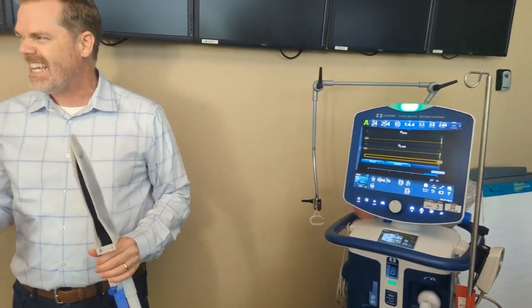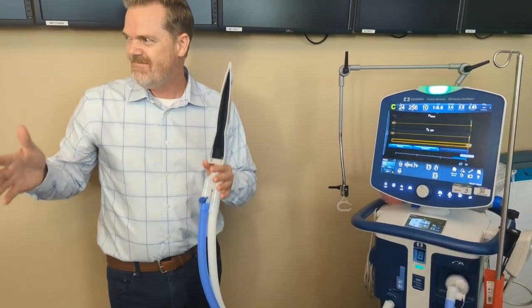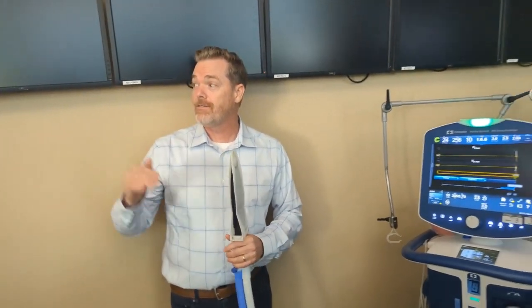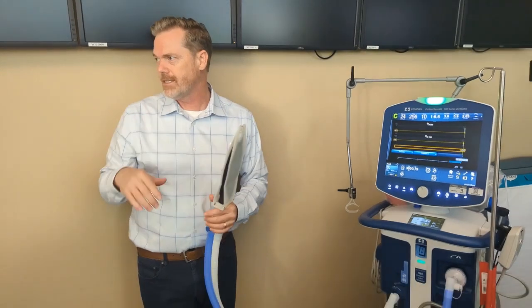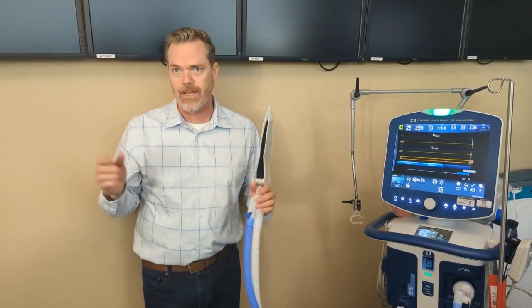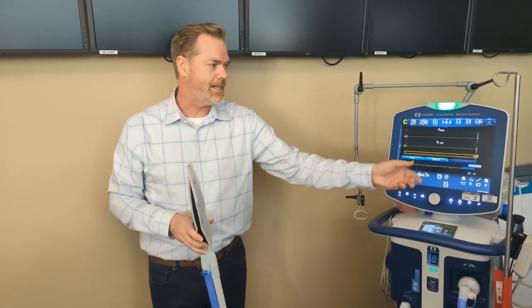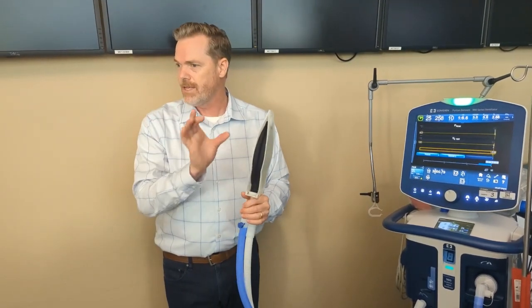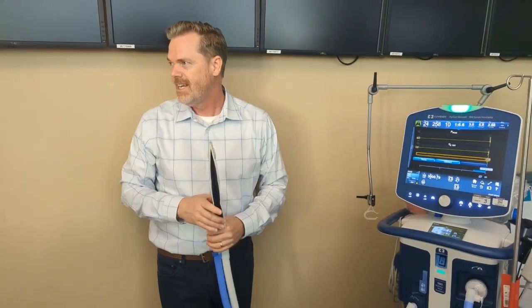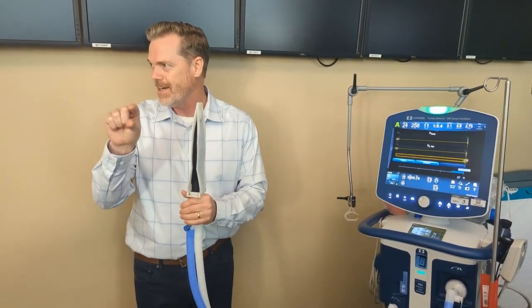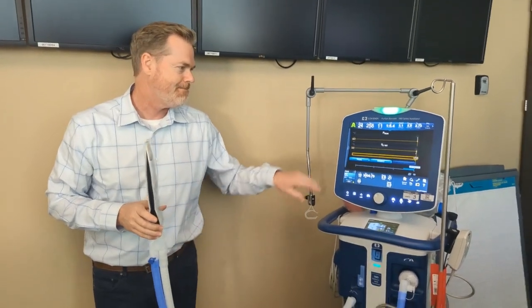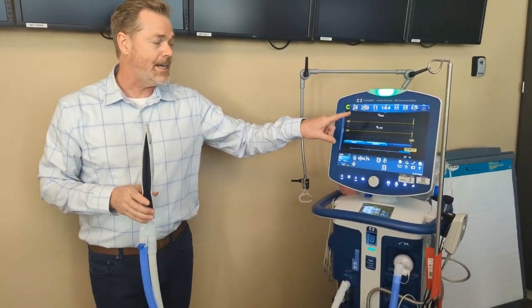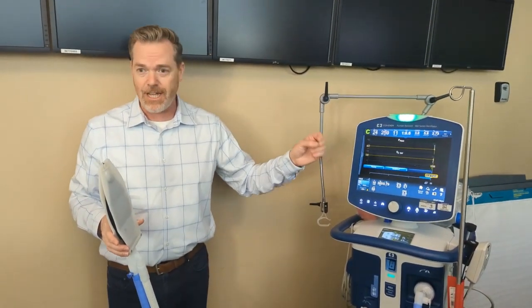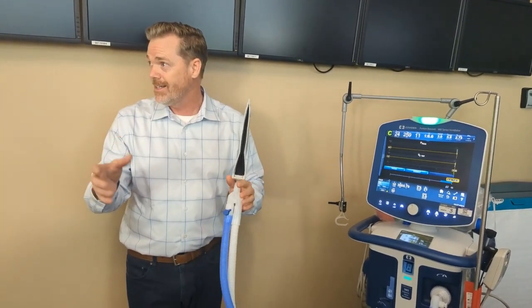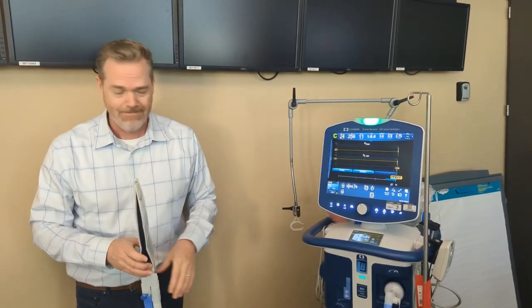If you have enough data on there from one of your patients to play with, the next time you have a patient on the vent for 3 or 4 or 5 days, just go and select that, dial that in, and you can see that it'll pull up a window of just 12 hours. It's easier to see some of that data. Connect the high pressure O2 hose to the back of the blender. That is our small backup system here, so we want to make sure that our high pressure O2 is connected in the back. Good question. And of course, trending is a capability with a lot going on here, so it can get a little confusing.